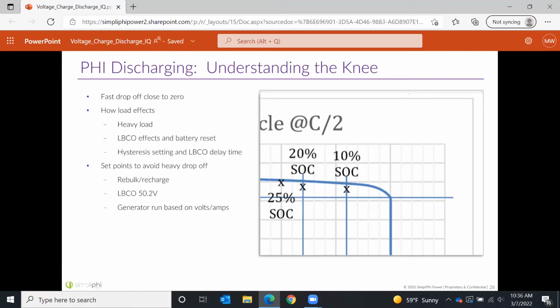Another thing you can do to prevent hitting this knee hard is starting a generator when the voltage is beginning to drop. Most newer inverters have an AGS option built in that automatically starts your generator. You can set it to start at around 50.4 or 50.6 volts to prevent ever reaching low battery cutout. You can also have the inverter pull from the grid when the battery reaches that voltage, which is a good option if you're grid tied.